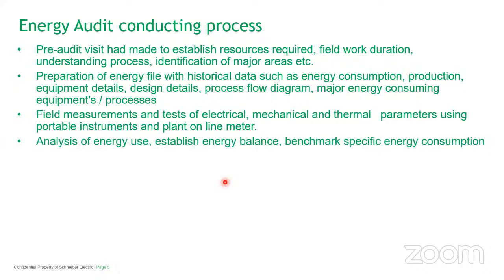Then we analyze the data. We see how the energy usage is happening, how the energy balance is. If I do the energy balance, it is basically that if the total main power coming into my house is, for example, 5 kilowatt, I should know who is consuming this 5 kilowatt. Maybe 1 kilowatt is consumed by the refrigerator, maybe 1 kilowatt by the geyser, or maybe some lighting loads. So we should know who is consuming the power. It's called energy balance.